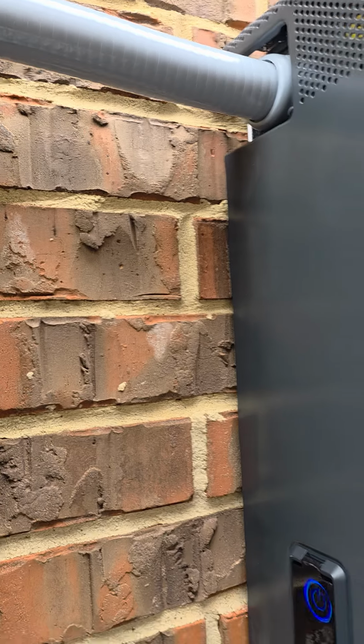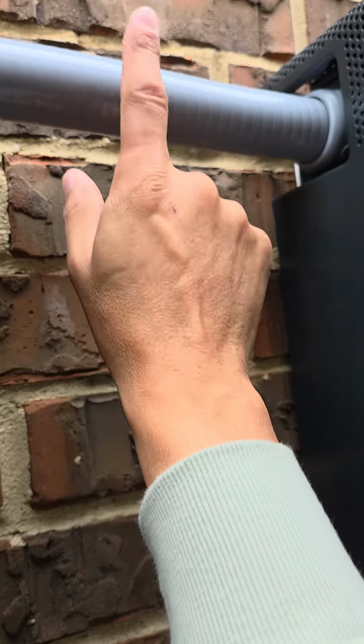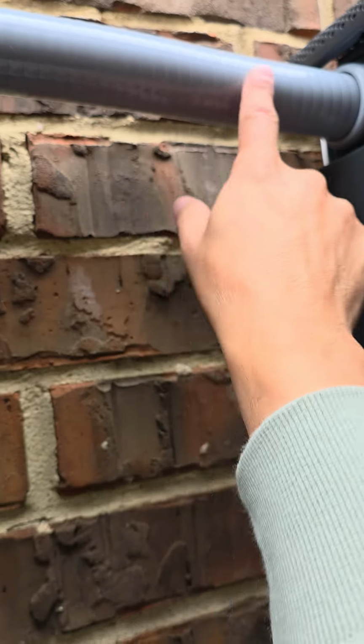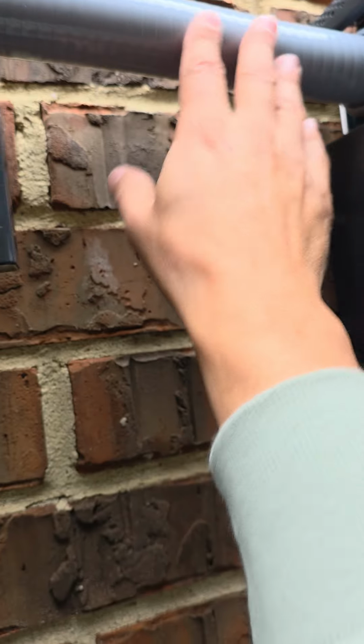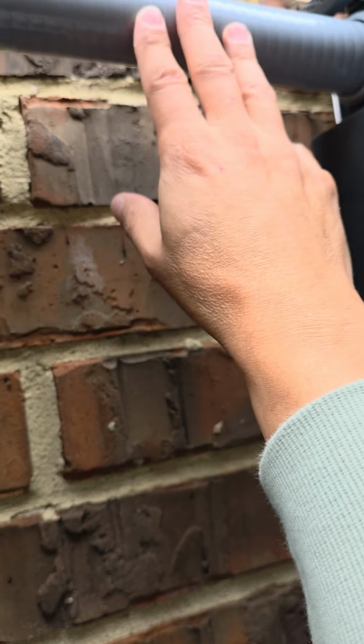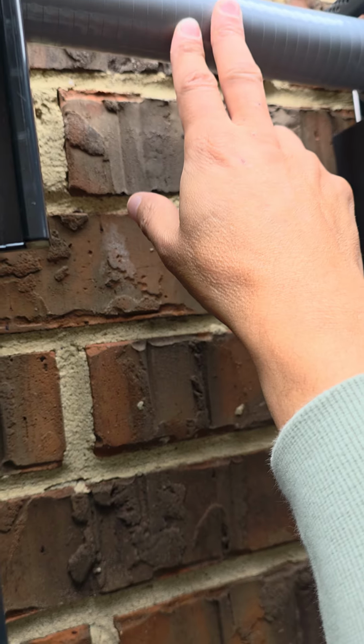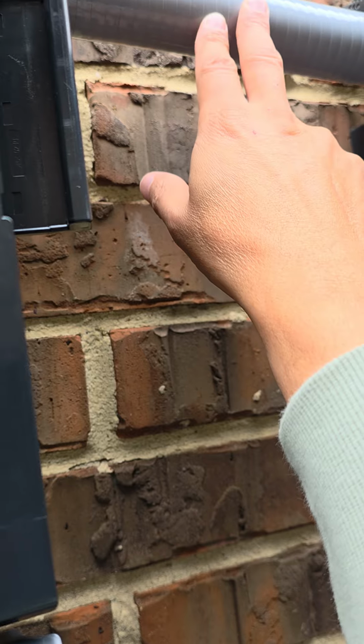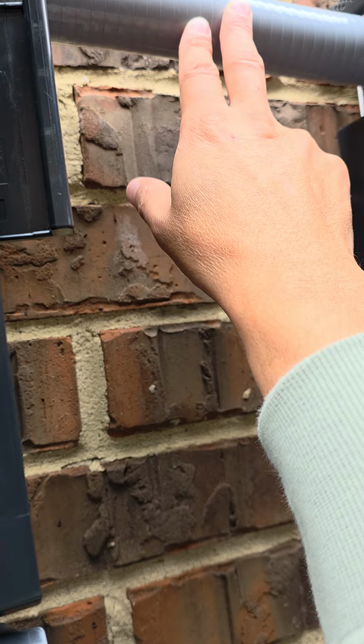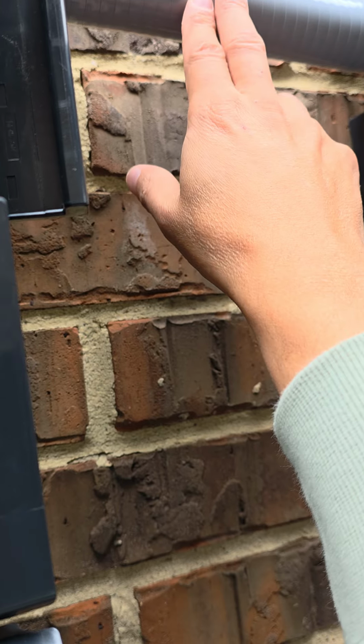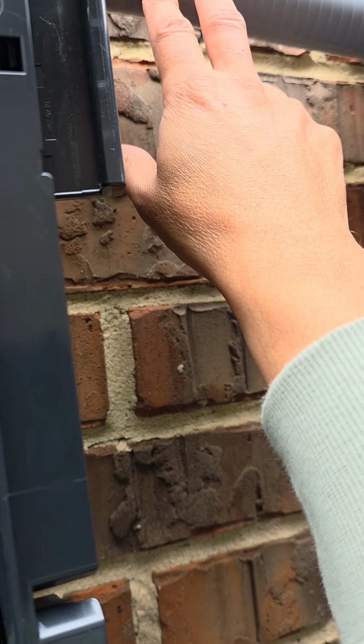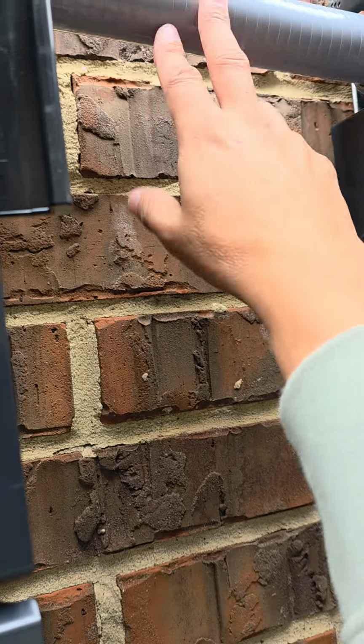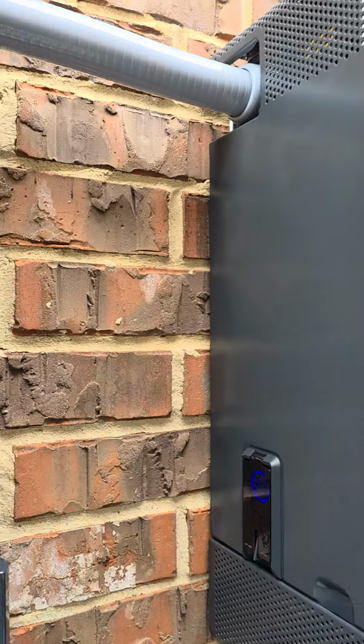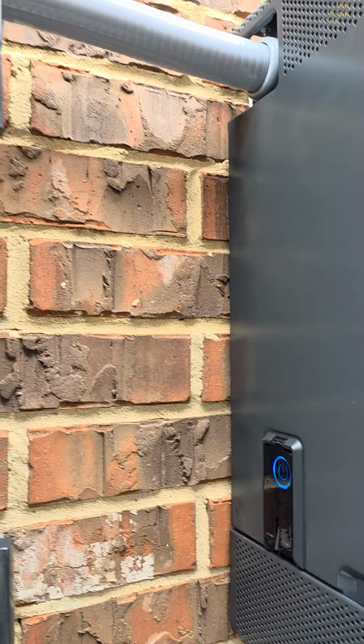Whenever you're doing an install, if you do the non-metallic conduit, just because it's sticky, kind of rubberized, make sure you run your COM cables first. They are equally as sticky. You do not want to run them last. If you do, they will not slide through this pipe whatsoever. They'll get stuck, and then you might tear them. So install tip: run your COM cables first, then run your electrical wiring.